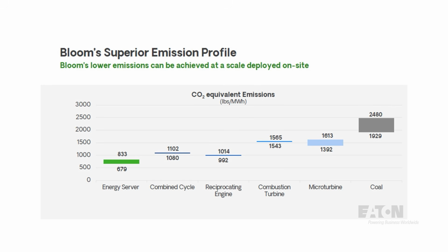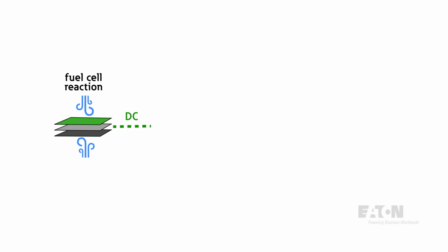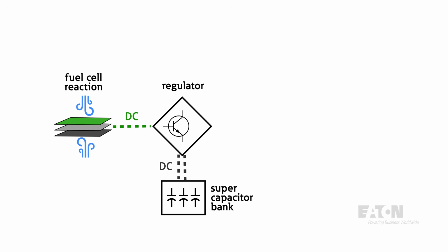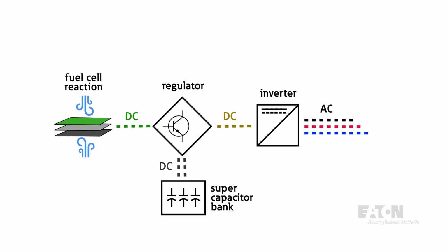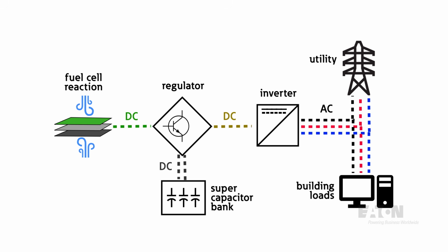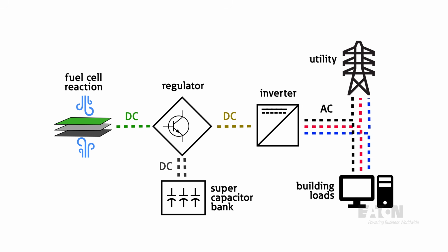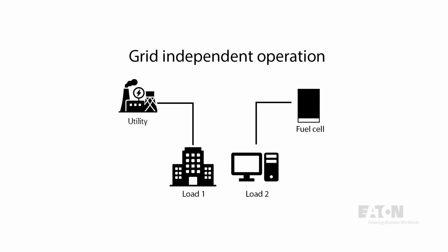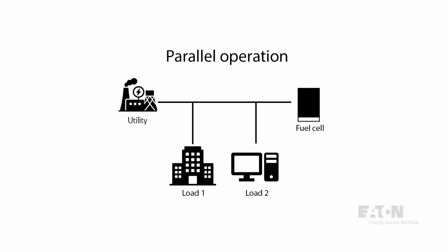And with carbon capture, it can capture 95% of the pure carbon dioxide stream and can be used for food-grade utilization or sequestration. Once the DC voltage is produced, it's regulated and supercapacitors are used to stabilize the voltage. Then it's inverted to AC to put power back onto the electrical distribution system. If it's operating independent of the utility, it sends the power directly to the loads. If it's operating in parallel with the utility, it can send power to the loads and the interconnected distribution system.